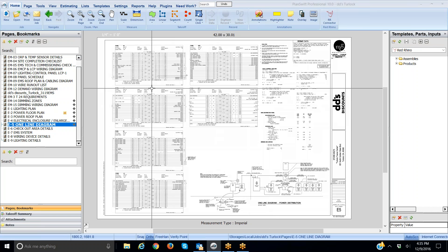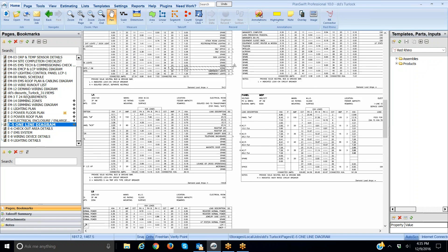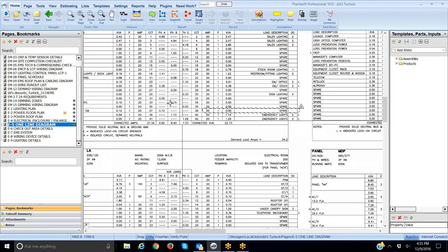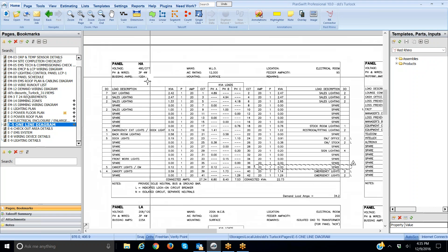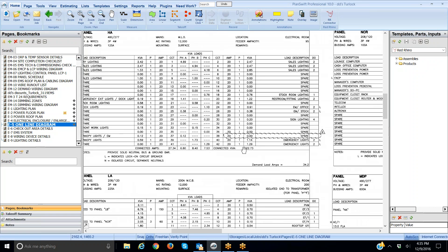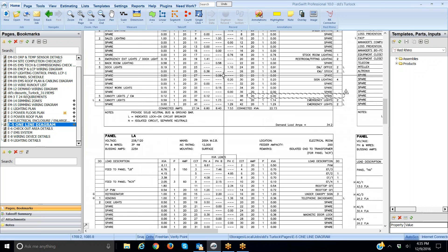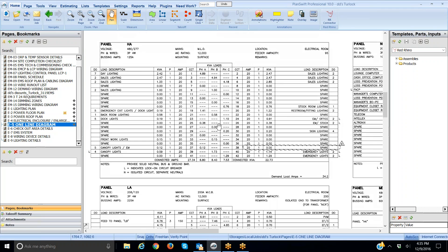This is where you want to take off your panels and circuit breakers or switchgear. I'm going to zoom in here a little bit and you can see I have several different panel sizes. This panel is a 125 amp, scroll over here this one's a 100 amp, scroll down this one's a 225 amp. So I'm going to take these off and also show you how to take off circuit breakers.